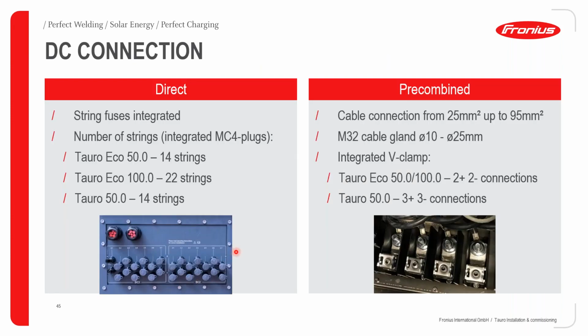For your DC connection, we have two possibilities, as my colleague David said earlier on. You get the direct and the pre-combined. With the direct, your string fuses are integrated. The number of strings for the Tauro Eco 50 kilowatt will be 14 strings. For the Tauro Eco 100 kilowatt it will be 22 strings, and for the Tauro 50 kilowatt it will be 14 strings. For your DC connections, here is an example for the Eco 50 kilowatts with the direct version. You can see your DC cabling goes directly from your panels, your strings, to the DC inputs on the inverter itself. So there are your positives and there are your negatives.